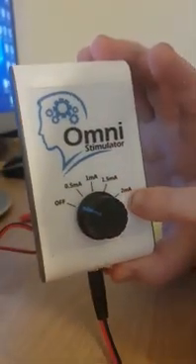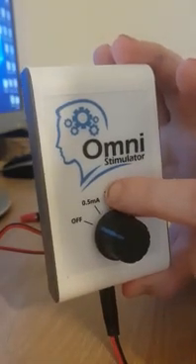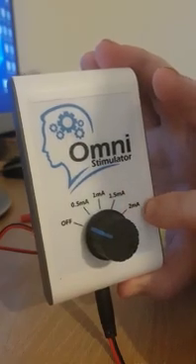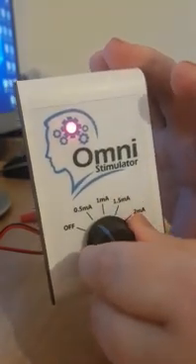The Omni Stimulator has a range of different amperage settings — starting from 0.5 milliamps, to 1 milliamp, 1.5 milliamps, and 2 milliamps — and you can set that as you want.